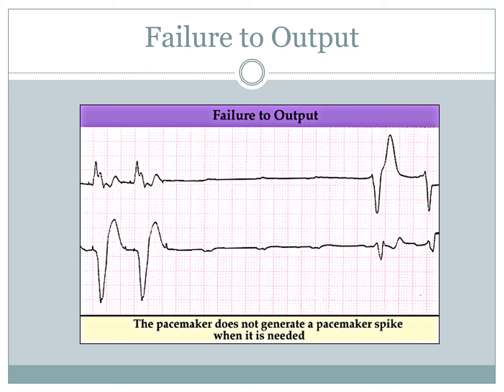Or you see in the bottom the same case. In fact, the pacemaker spikes in this one look very small. Okay, so there is failure for the pacemaker to generate a spike that's sufficient enough to result in a contraction. Look at that. You can imagine what's going on in terms of the patient's cardiac output during this time. Okay, I think we would institute an immediate temporary pacemaker if this were the case, because we need to get that pacemaker replaced. It's not working.